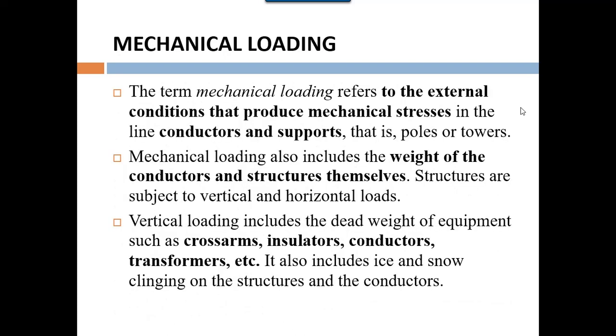The term mechanical loading refers to an external condition that produces mechanical stress in the conductor and supporting structure — that is, the pole or tower. Mechanical loading includes the weight of the conductor and the structures themselves. Structures are subjected to vertical and horizontal loads. The vertical load includes the dead weight of equipment such as cross arms, insulators, and conductor transformers. It also includes ice and snow clinging to the structure. While designing the mechanical structure, we should consider that the pole has sufficient strength to handle these kinds of issues.